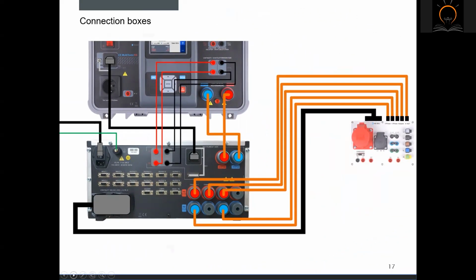The connection box is a passive device that acts as a connection interface between the CE switch A1600 and the equipment under test. It is intended for connection of various types of appliances to A1600 CE switch. Equipment with supply cords or equipment intended for fixed installation can be tested. The connection boxes are coded to prevent applying a too high test voltage to its outputs.